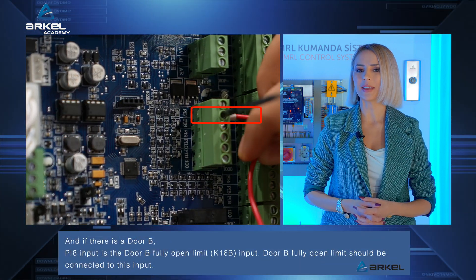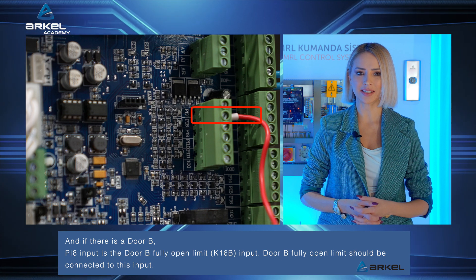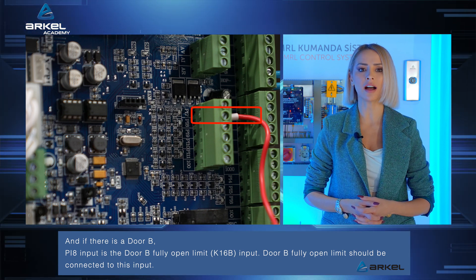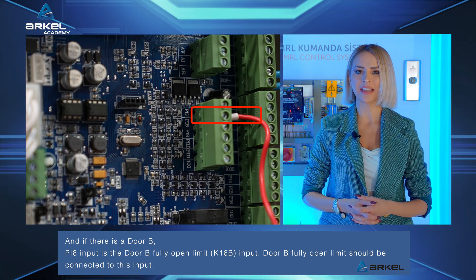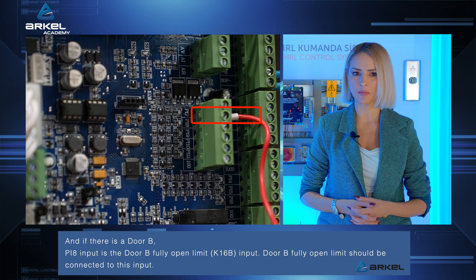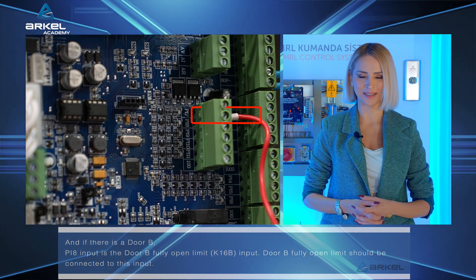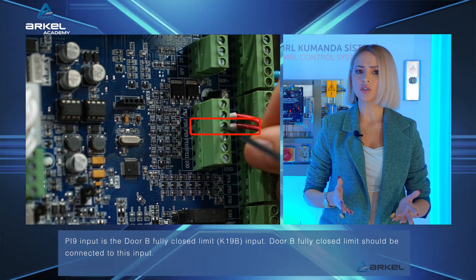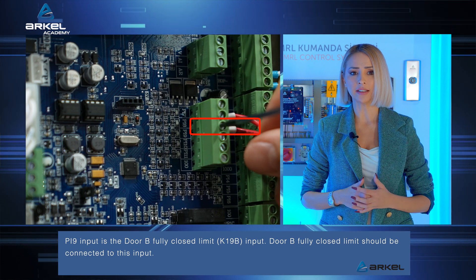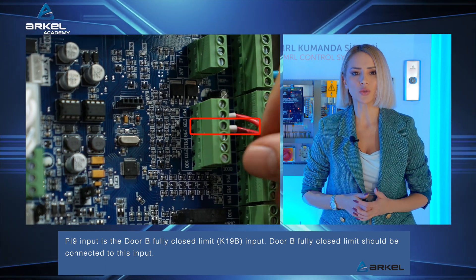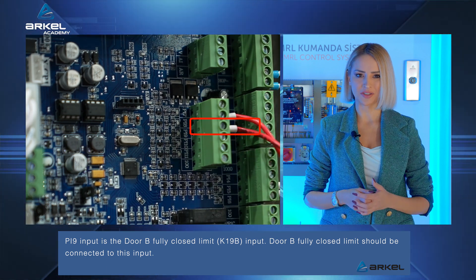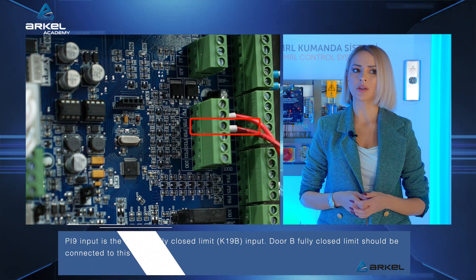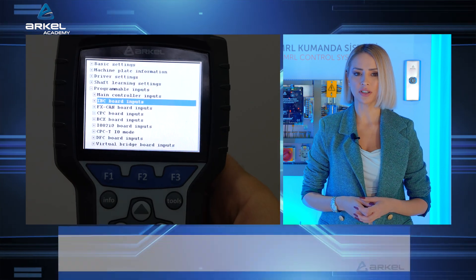If there is a door B, PI8 input is the door B fully open limit (K16B input) — door B fully open limit should be connected to this input. PI9 input is the door B fully closed limit (K19B input) — door B fully closed limit should be connected to this input. For all connection types, 100 — in other words, plus 24 — should be used for the common supply of the limit switches.